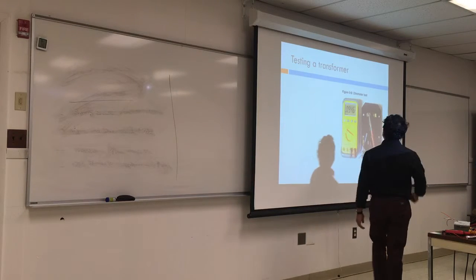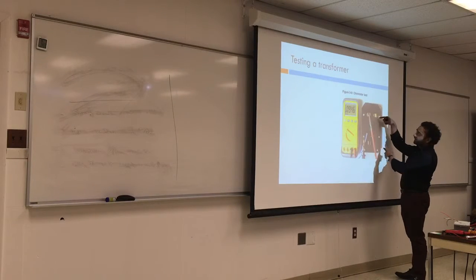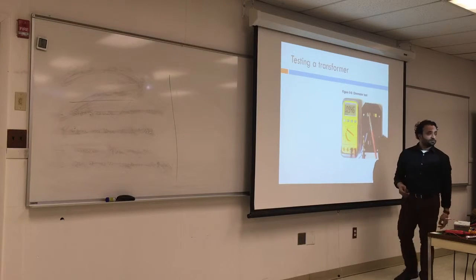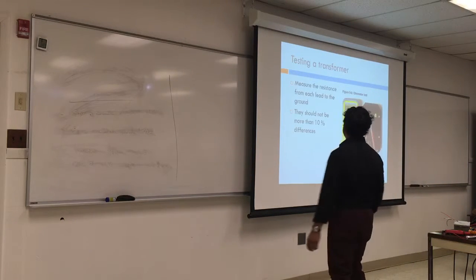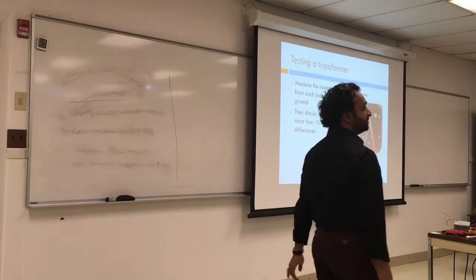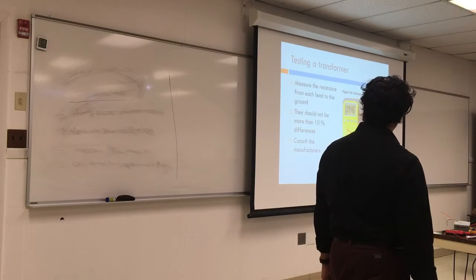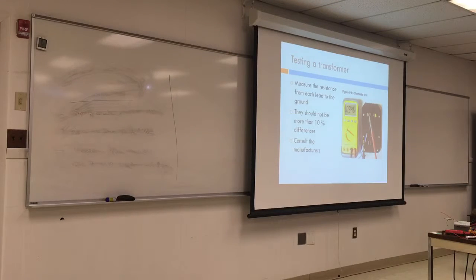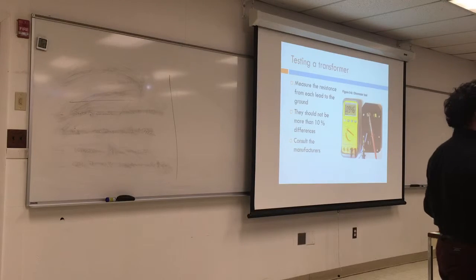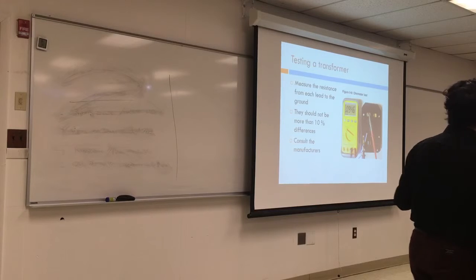Again, this is another method. Compare the resistance between each lead and the ground. And again, 10% is acceptable as a difference between the resistance. We did that lab last semester where we tested a transformer. If you ever forget and you want to test a transformer, you can go back to the PowerPoint, or you can YouTube how to test a transformer. And the best way actually is to contact the manufacturer or look at the manual, or sometimes check the model number. But these are ways to measure to see if the transformer is running or not.